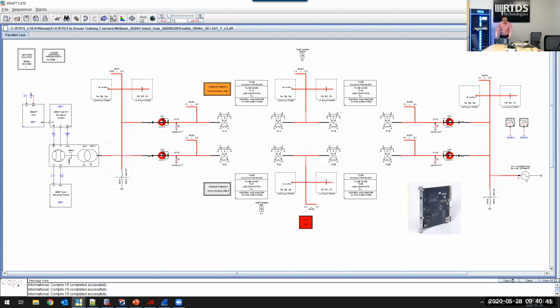Now, this is the relay we're using. On the back of the relay, there are only 3 cables besides the power cable. Two of them are Ethernet cables, one for the station bus communications, and the other for the process bus communications. We also have a BNC cable connected to the relay, which is provided by the GT Sync. The GT Sync works as a master clock in this demo, providing the IRIG-B signal to the physical relay.